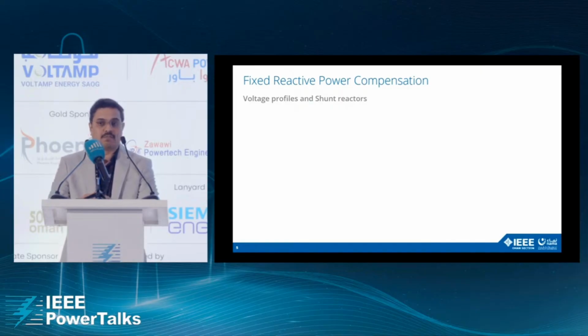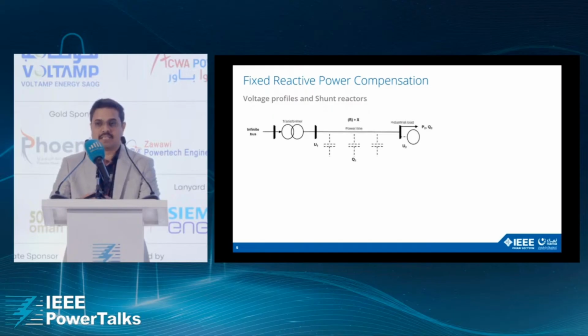Now we can discuss the voltage profiles under different demands for reactive power. Again, we have a single line diagram of this power network. We have the infinite bus, we have the transformer, and a transmission line with the capacitance. Here, Q1 is the total reactive power induced in the transmission lines. Under normal circumstances, the total reactive power generated by the system and the total reactive power consumed by the industrial load, Q2, will be constant. Then the voltage at the sending end, V1, and the voltage received at the consumer level, V2, will be constant because we don't have any reactive power unbalance.